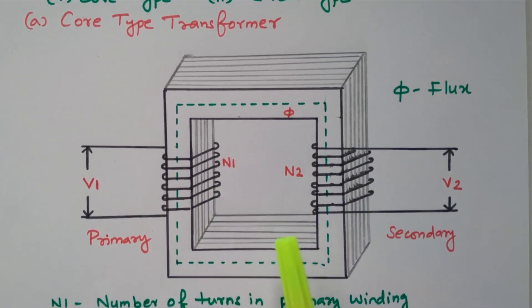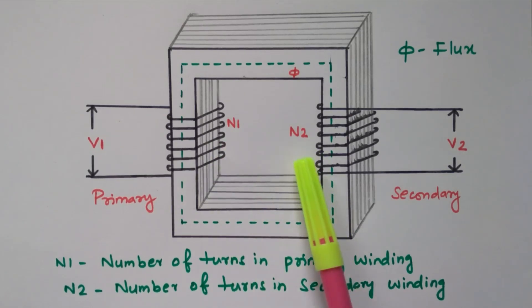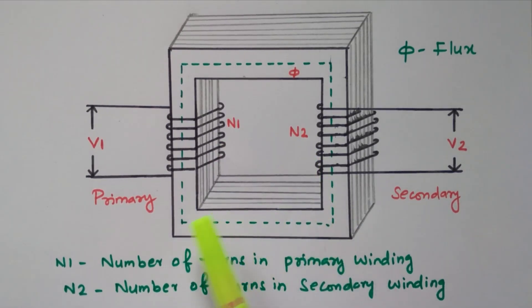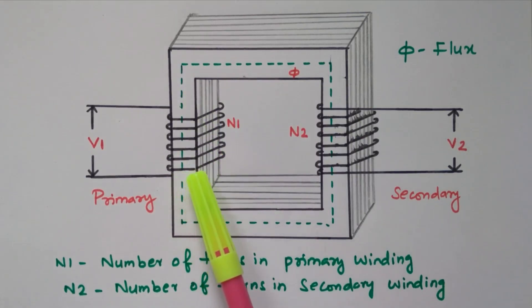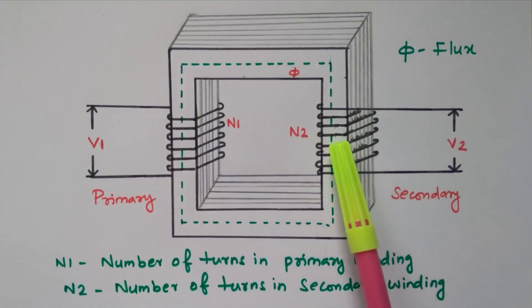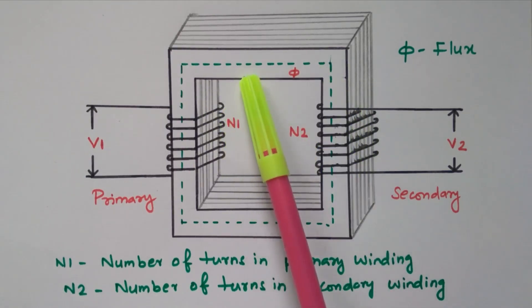N1 is the number of turns in the primary winding and N2 is the number of turns in the secondary winding. In the core type transformer, the winding surrounds the core. The windings are placed first, and over the winding the core sheets are placed one by one — both the horizontal and vertical cores are joined and placed over the winding. So we can easily remove the core since the winding is fixed.